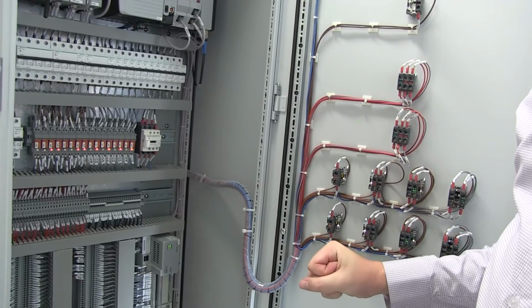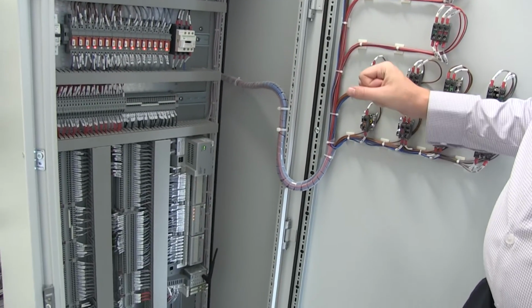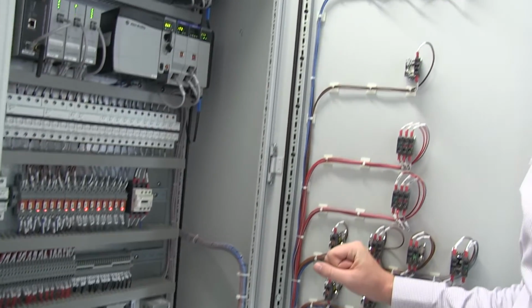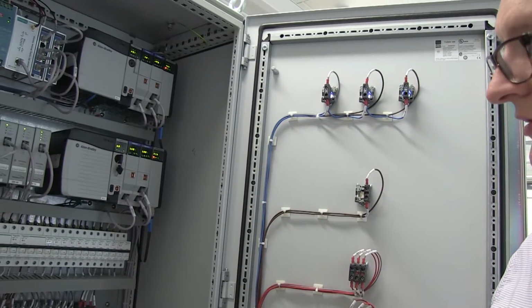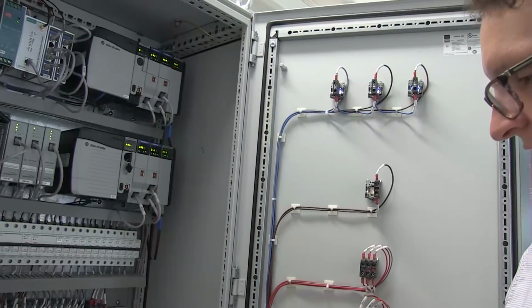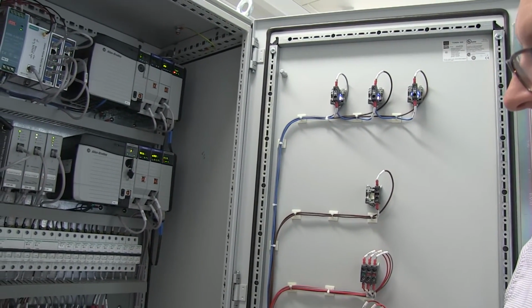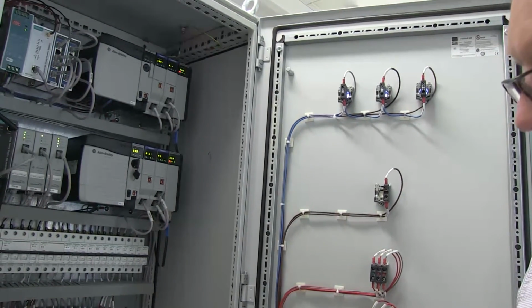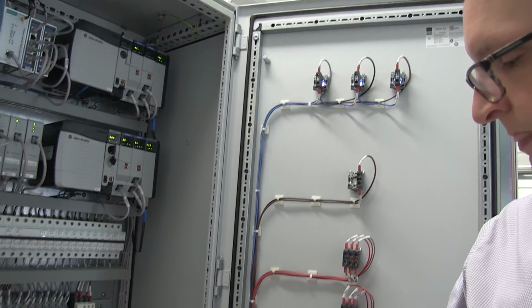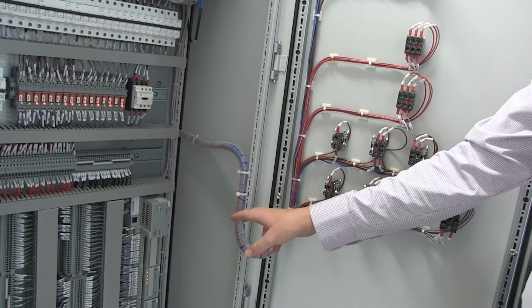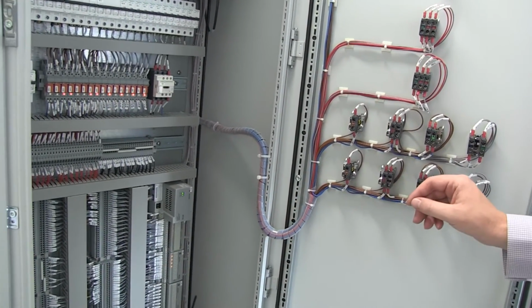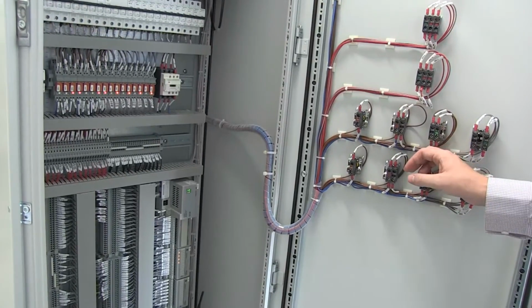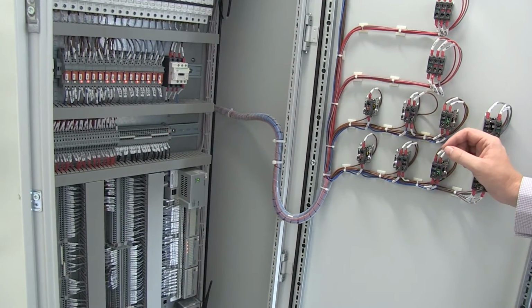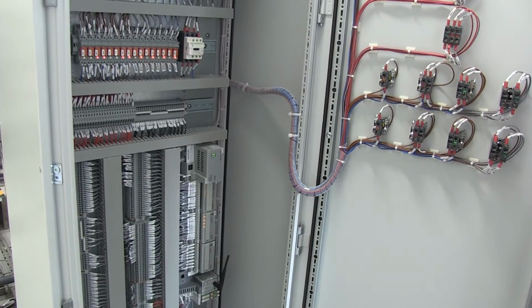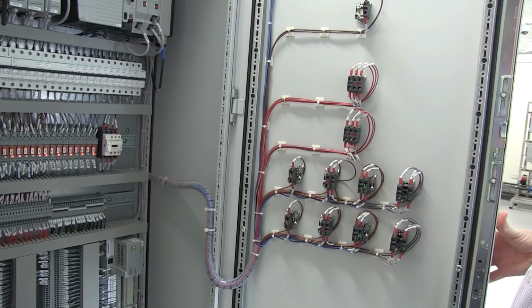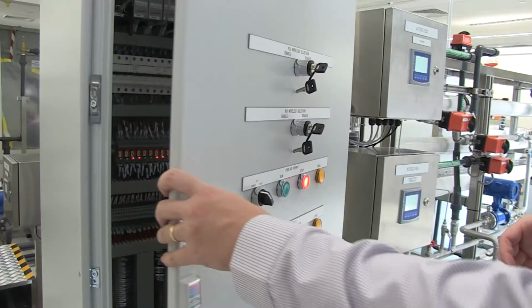In this case, the PLCs don't directly have I/O units, so they can't receive analog signals or send digital or analog signals. To communicate with the sensors and actuators, the PLC will send messages over the level 0 ring to the remote I/O, and the remote I/O then translates them into analog signals. In both the level 1 and the level 0 network, we mainly use wired network connectivity. We are always able to switch into a wireless connectivity mode by essentially flipping a switch which is provided on the casing.